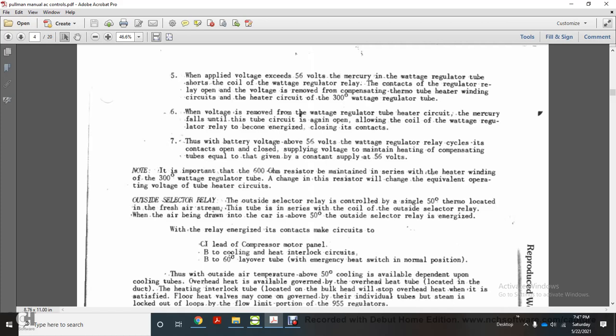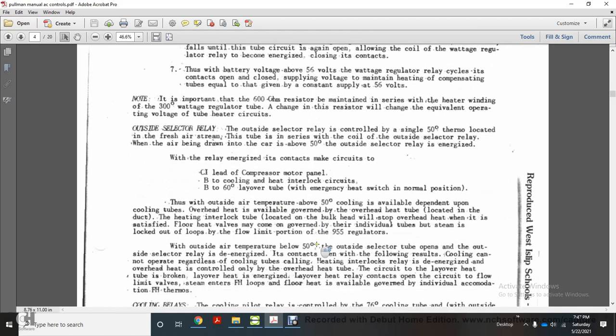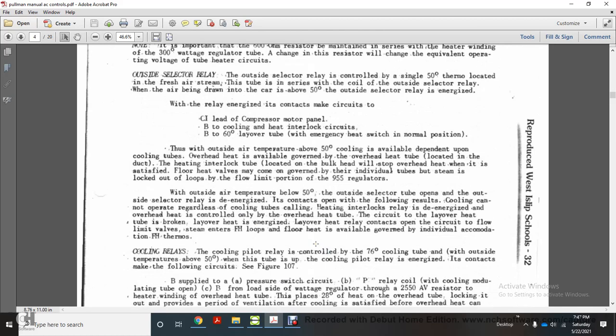When the outside selector relay is energized, the relay contacts make a circuit to the C1 lead of the compressor motor panel, enabling cooling and heating interlocking with a 60-degree layover tube, with the emergency heating switch in the normal position. With outside air temperature above 50 degrees, cooling is available depending on the cooling tubes; overhead heat is also available governed by the overhead heat tube located in the duct.